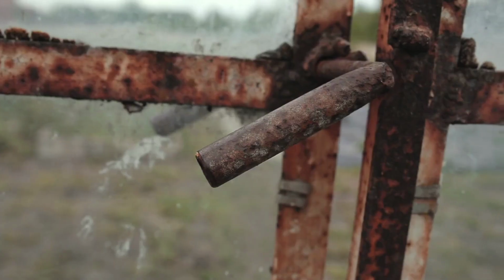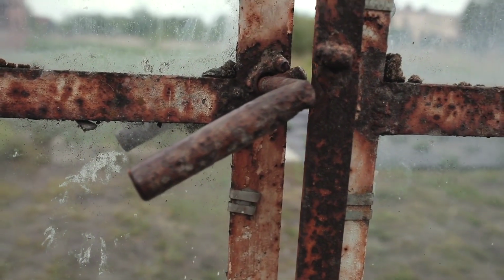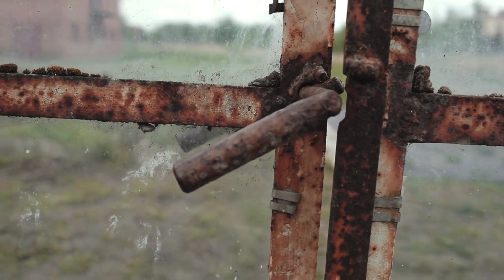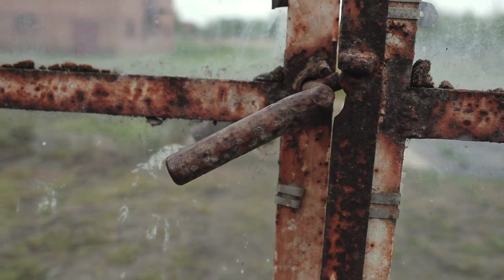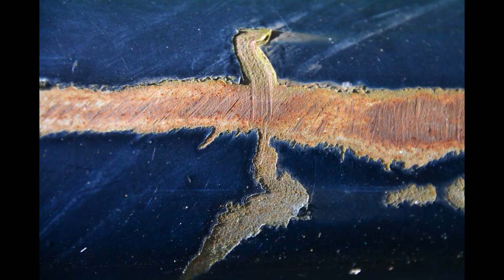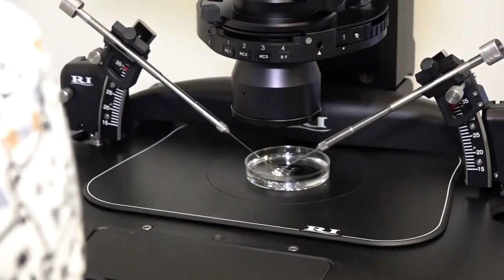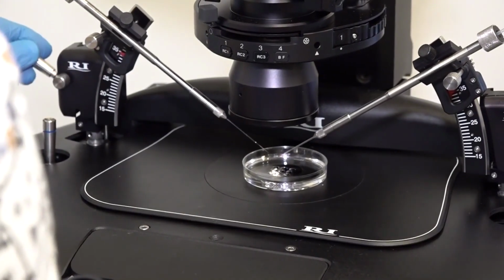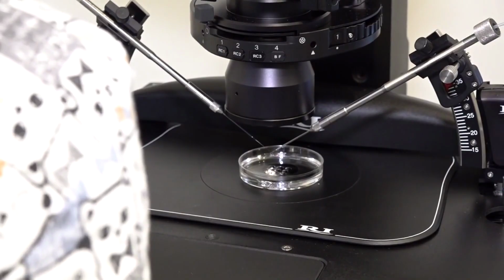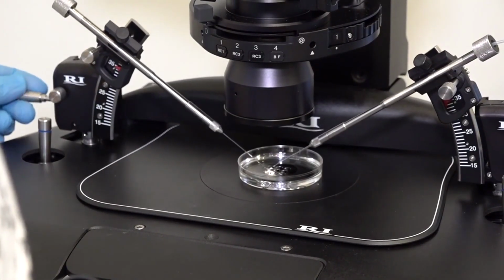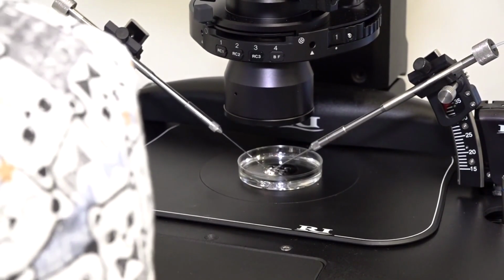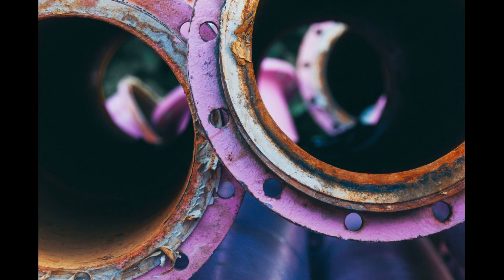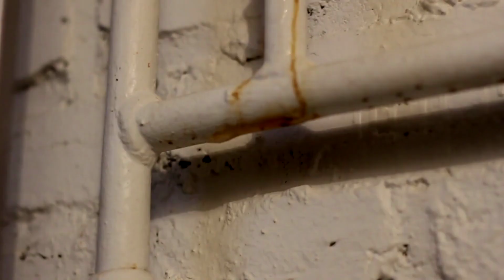The system safety protocols trigger, chips throttle back, performance plummets, and those billion-dollar training runs slow to a crawl. If nobody catches it fast, the system shuts down entirely to prevent permanent hardware damage. Technicians get called in. They drain the entire cooling loop, flush it with special solutions, replace corroded components, refill with fresh treated coolant. That's 5 to 6 hours of complete downtime. In a hyperscaler running billions of dollars of AI work, 5 hours isn't annoying, it's catastrophic. We are talking millions lost per hour.